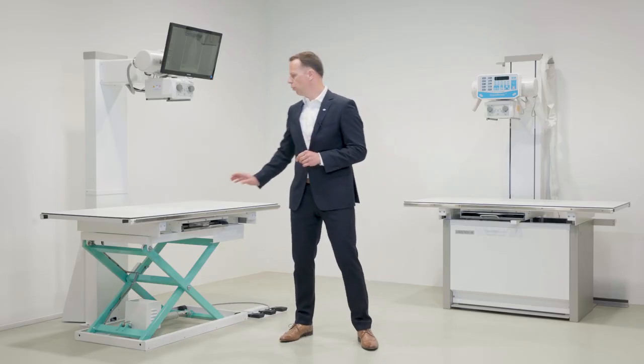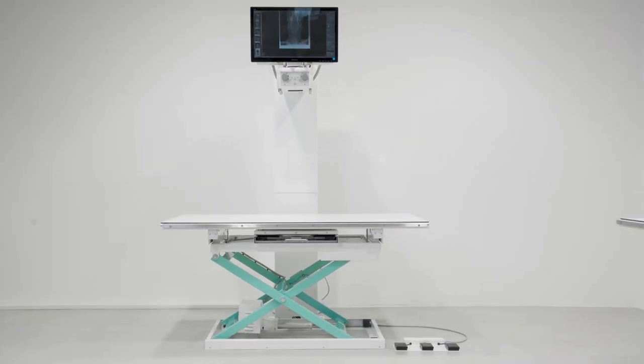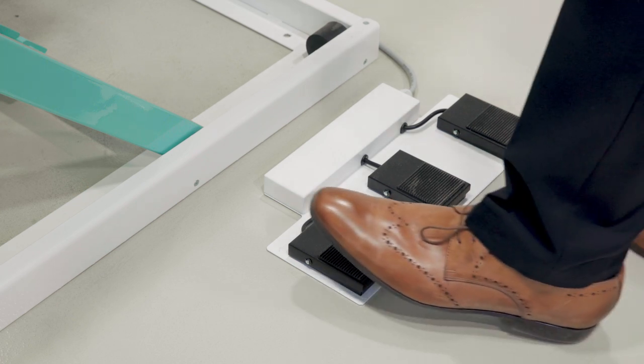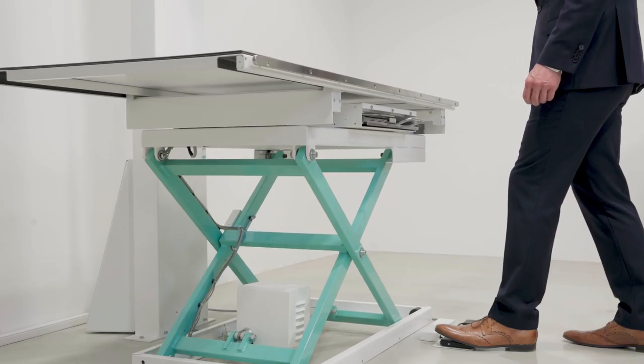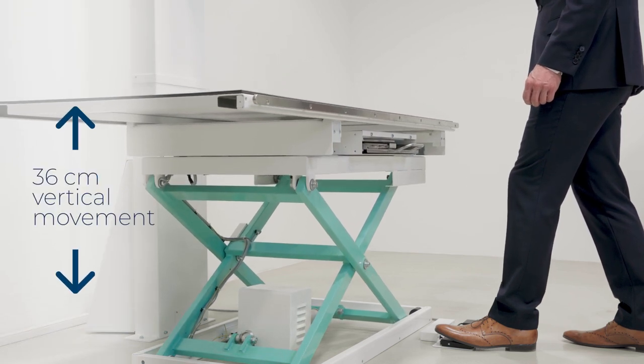Let me first show you the ZoomX Gold system. The ZoomX Gold is a fixed tube setup which comes with either the standard fixed height table or a brand new Vetelev table. The new table is a simplified and cost-conscious version of a popular Phoenix medical patient table. It easily lifts over 100 kilograms and has a vertical movement of 36 centimeters.